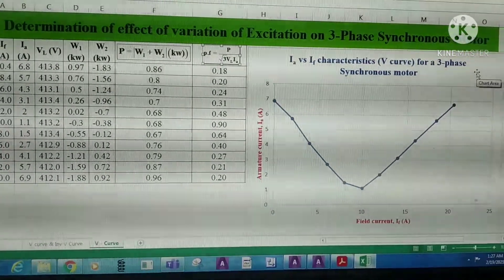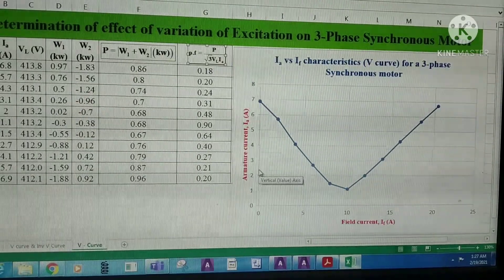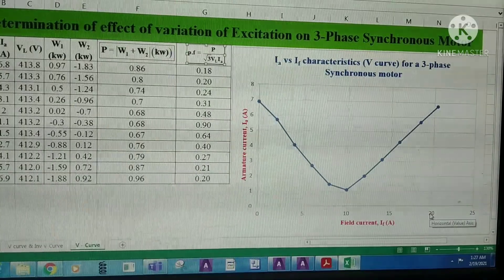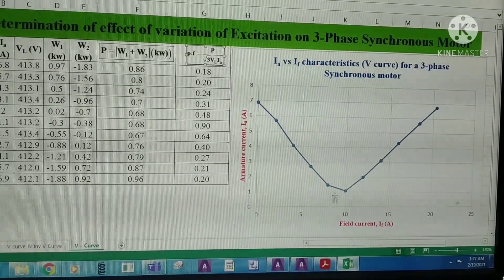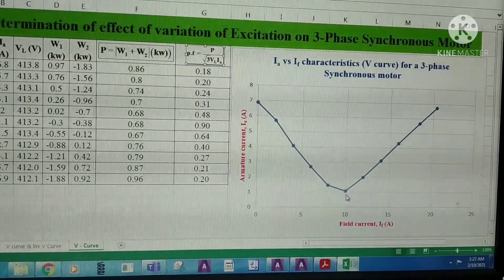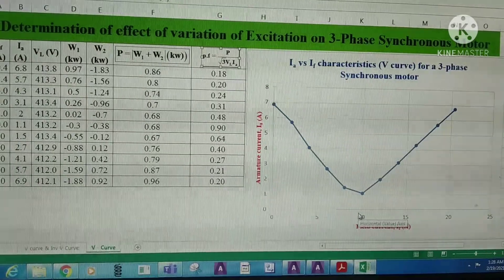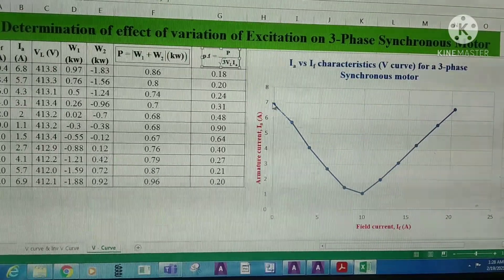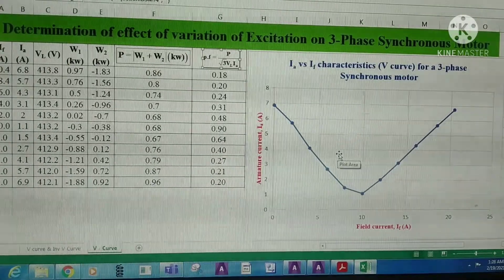If we observe the plot, on the X-axis we have the field winding current in amperes and on the Y-axis we have the armature current in amperes. If we decrease the field current from 20.4 amperes to 10 amperes, then armature current decreases from 6.76 amperes to 1.06 amperes. If we decrease the field current further from 10 amperes to 0 amperes, then armature current increases from 1 ampere to 6.9 amperes. The shape of this characteristic curve is the V-curve for a 3-phase synchronous motor.